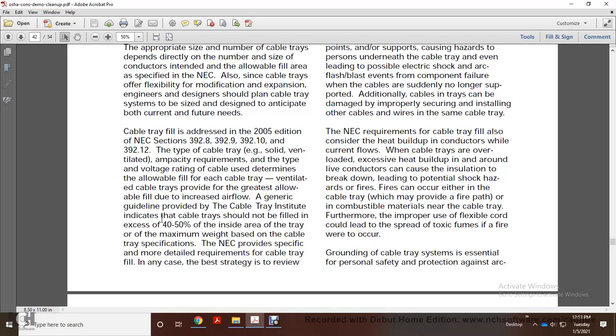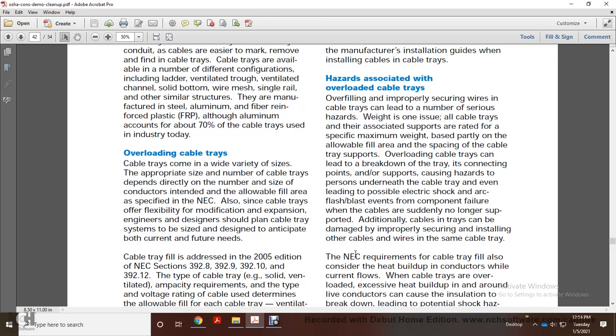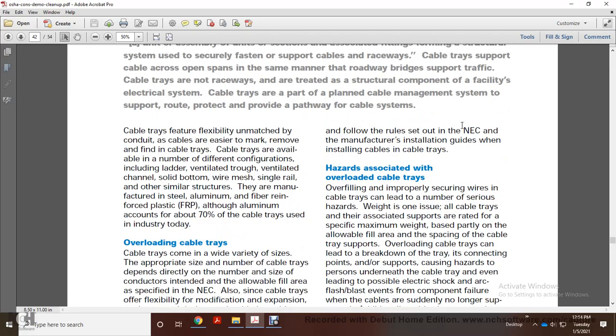Ventilated cable tray provides the greatest allowable fill due to the increased airflow. Generic guidelines provided by the Cable Tray Institute indicate that a cable tray should not be filled beyond 40 to 50% of the inside area, with a maximum weight based on the cable tray specification. The National Electrical Code provides more specific and detailed requirements for cable tray. In any case, the best strategy is to review and follow the rules set out in the National Electrical Code and the manufacturer's installation guidelines when installing cables in the cable tray.